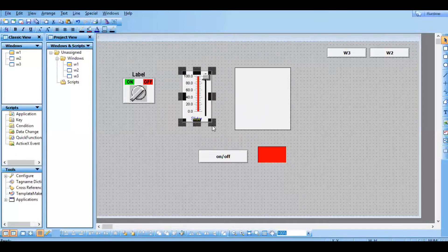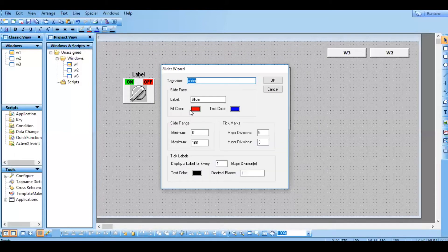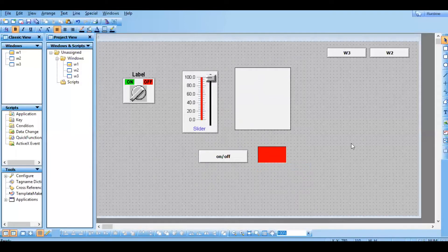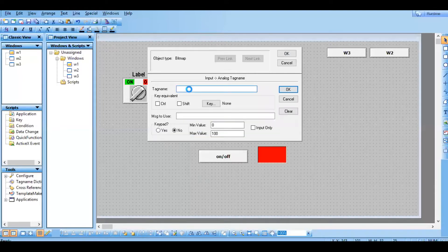For analog touch link, we need to assign it to the slider. But when you click on the slider, it does not open the animation link. You need to break the slider first. Once you have done the break, click on the slider - it will take you to the animation link page. Go for analog, click on that, and choose the same slider tag. I'll go with the defaults, just giving the tag name. Go for OK, go for runtime.